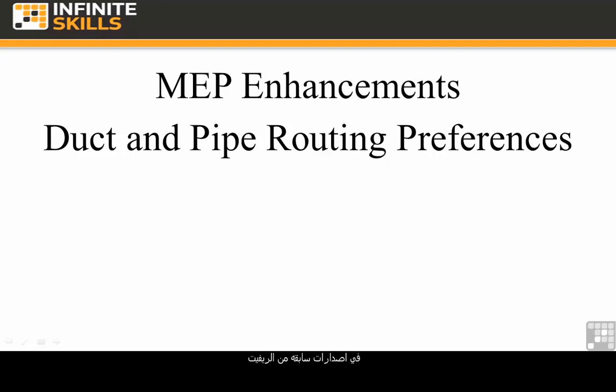In previous versions of Revit MEP, you had to create a duct or pipe type to suit all instances of the types of runs you were creating. So, for example, if your pipe had a specific fitting for a material at sizes 16 to 40 millimeters, and then another fitting from 50 to 100 millimeters, you'd have to have two different pipe types. In Revit MEP 2013, this is handled by segment. Let's take a look at that.